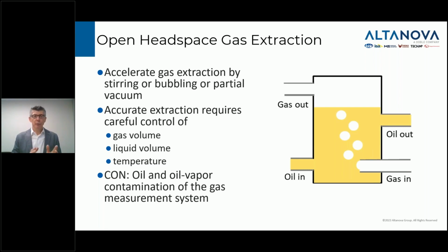These techniques require careful control or careful measurement of the volume of gas and the volume of oil. That ratio of those two volumes is a key parameter in the accuracy of the reading. The only thing with these is there is a downside, which is that in that headspace, in that vapor above the oil, there's always a bit of oil vapor, and the vapor pressure of that oil is there. So there's the possibility with these type of extraction systems that over time oil vapor migrates into the gas measurement system, which is not what you want. Normally you want a gas measurement system to be pristinely clean.